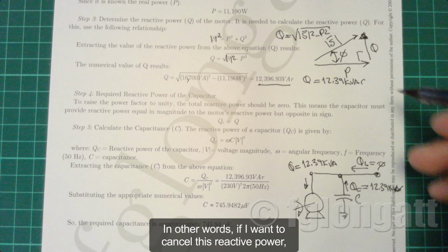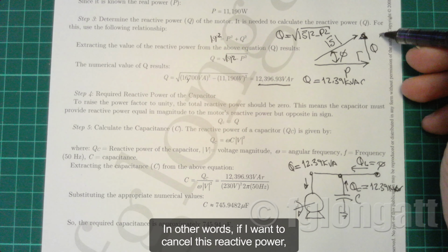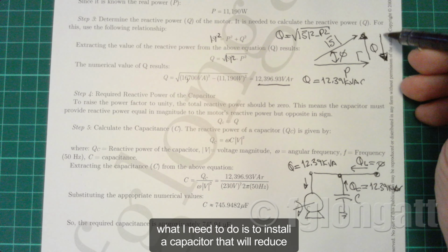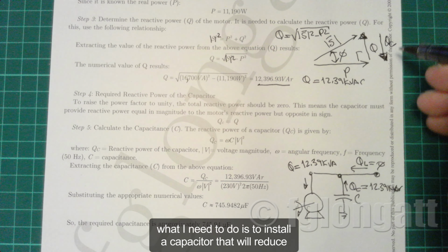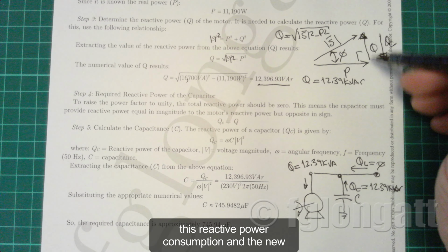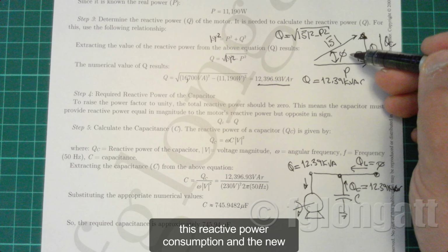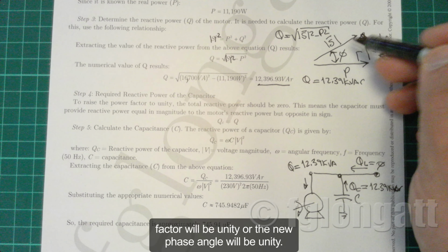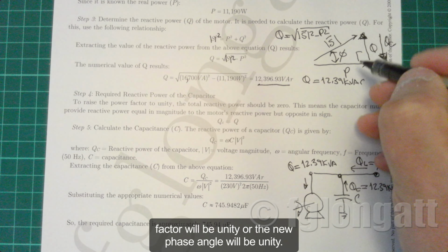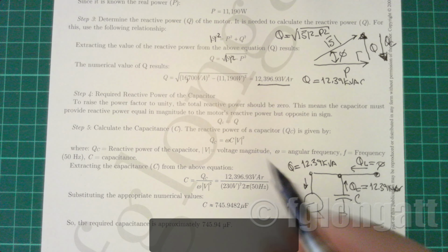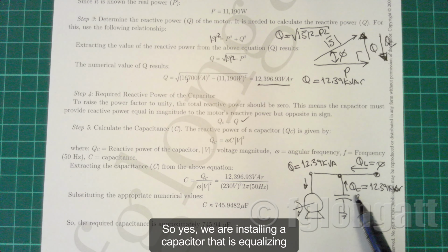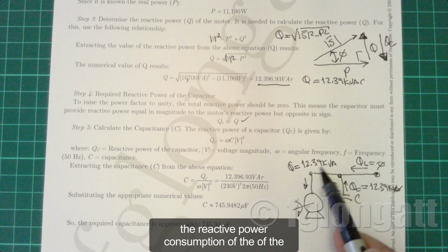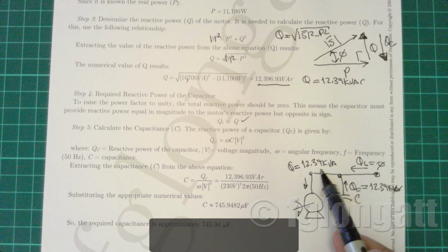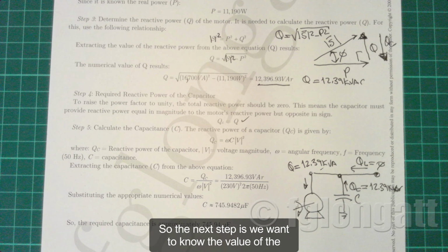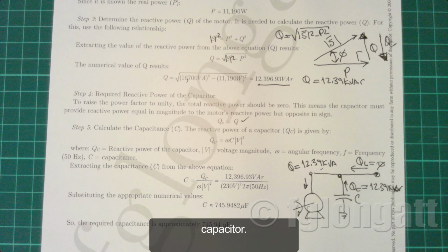In other words, if I want to cancel this reactive power, what I need to do is to install a capacitor that will reduce this reactive power consumption, and the new power factor will be unity, or the new phase angle will be 0. So yes, we are installing a capacitor that is equalizing the reactive power consumption of the motor.